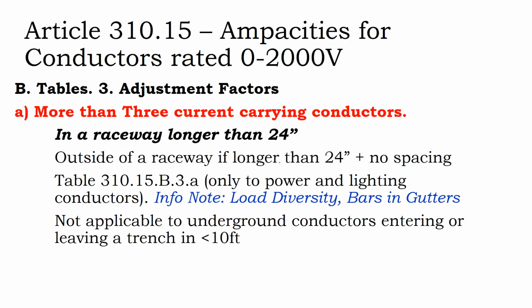And generally we're splitting hairs by the time that we're deciding between 2-aught and 3-aught, between the smaller wire and the larger wire. At this point in design, more than likely you're going to go with the larger wire anyway because of voltage drop, and then you might have to make a decision between that larger wire and the next larger wire, at which point it's not really an amperage decision anyway. It's more of a voltage drop consideration. Usually when you design by amperage, you're going to get to the minimum allowable wire, and then you upsize from there to accommodate voltage drop. Can my wire safely carry all the current that's going to be pushed through it, and then can I do that more efficiently by upsizing?